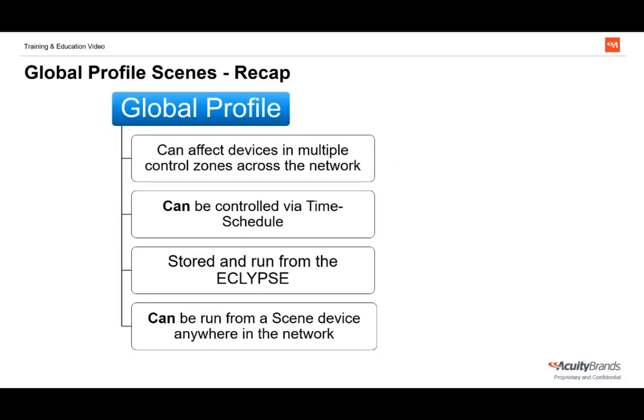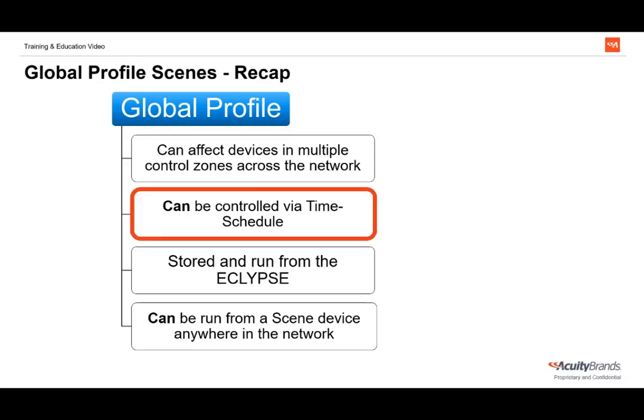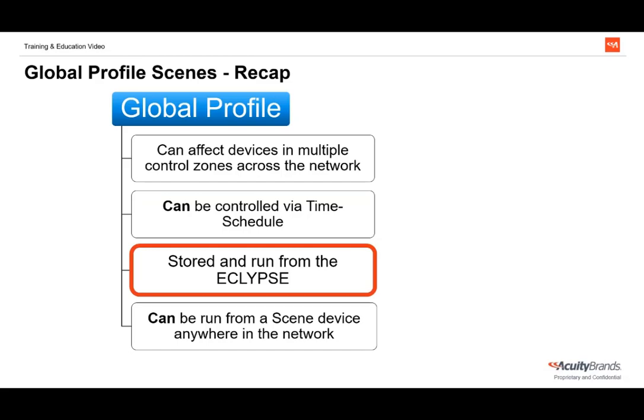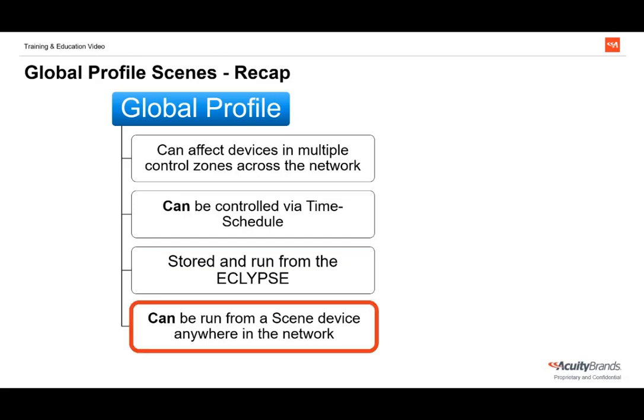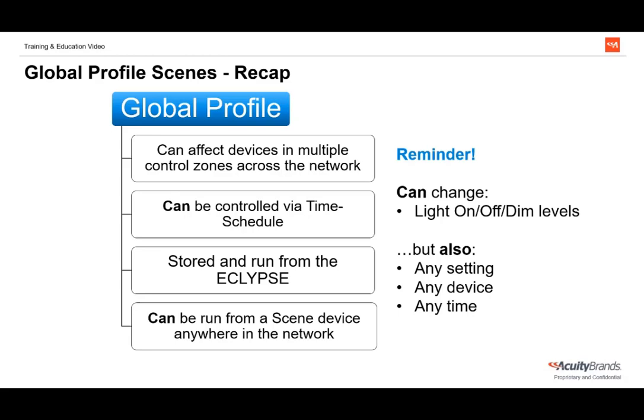Let's quickly recap global profiles. They can affect devices across the whole network, ranging from simply one device to every single device. They can be controlled by a time or astronomical schedule, and they are stored on and run from the ECLYPSE — so global profiles are only available on a fully networked system. If a profile is not on a time schedule, it will need to be run from a scene controller or directly from SensorView. Remember that profiles can change any setting of any device, not just light levels.